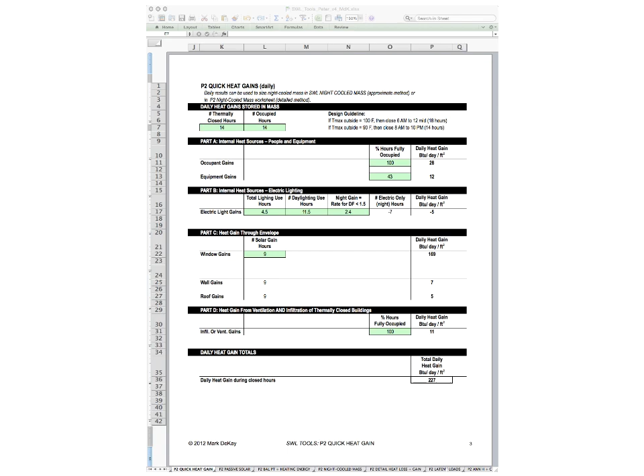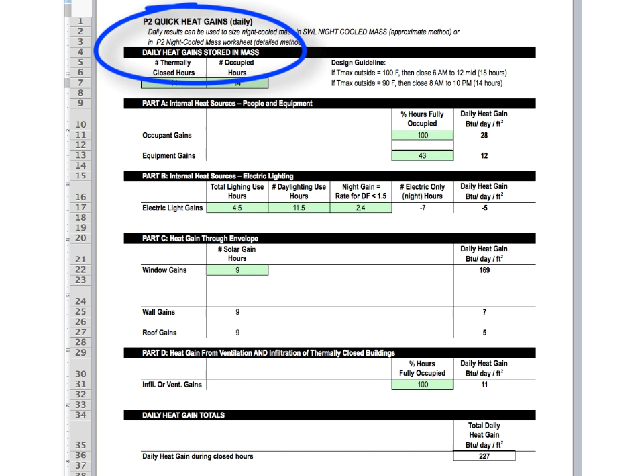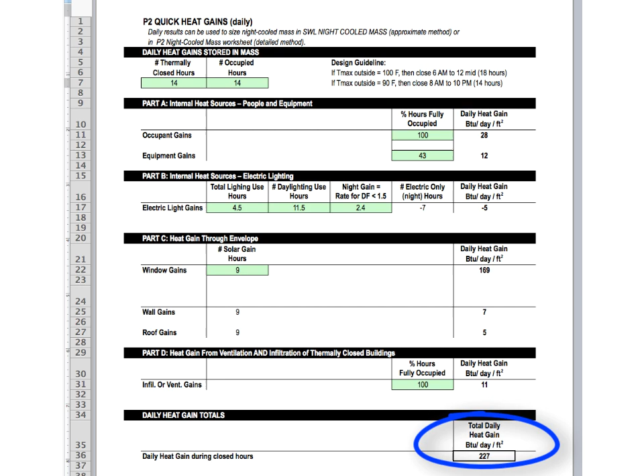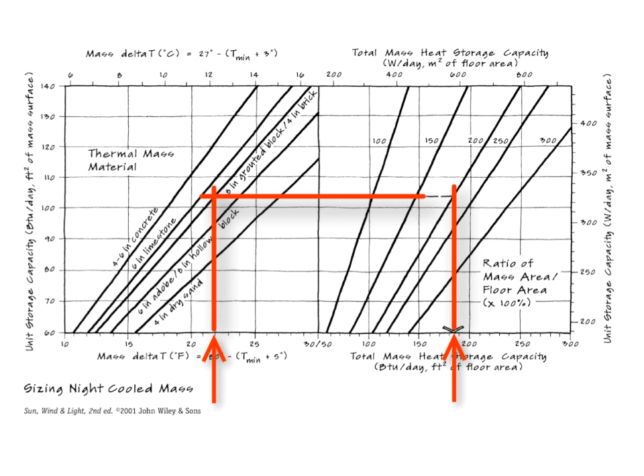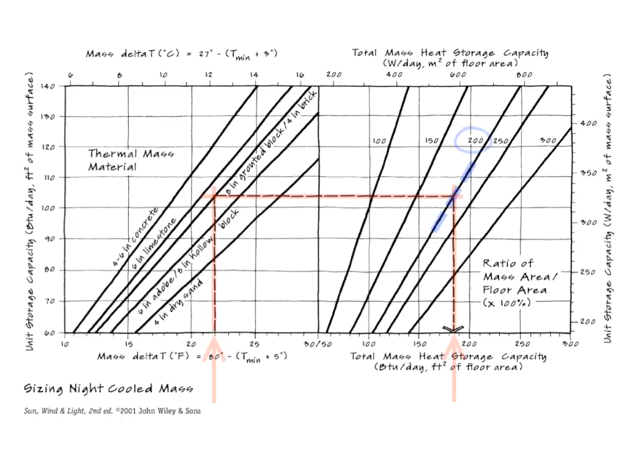So if we want to solve for how much mass we need, we first go over and find the rate of daily heat gain that needs to be stored in the mass. We can find that out in the SWL tools, looking at daily heat stored. We're taking a look at the quick heat gain page, and we can also look at this on the detailed heat gain page. If we know the total heat storage necessary on a daily basis, we can start there on the bottom axis and simultaneously on the left-hand side with the mass delta T, and intersect both pathways to find the required amount of mass.